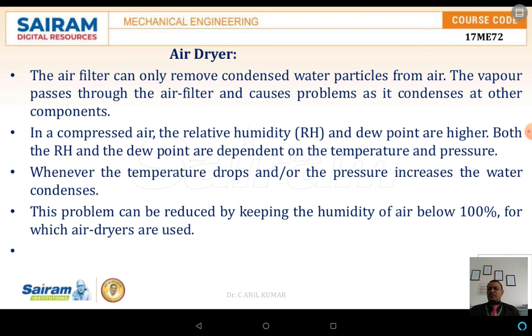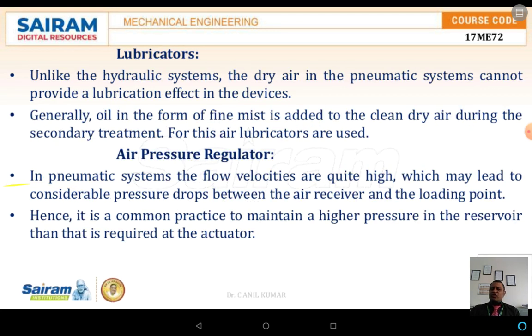Next, the air dryers. Air filters can only remove the condensed water particles from the air. The vapors pass through the air filter and cause problems as they condense at other components. In compressed air, the relative humidity and the dew point are higher, and both depend upon the temperature and also the pressure. When the temperature drops or when the pressure is increased, the water starts condensing. The problem can be reduced by keeping the humidity below 100%, for which air dryers are used in the line.